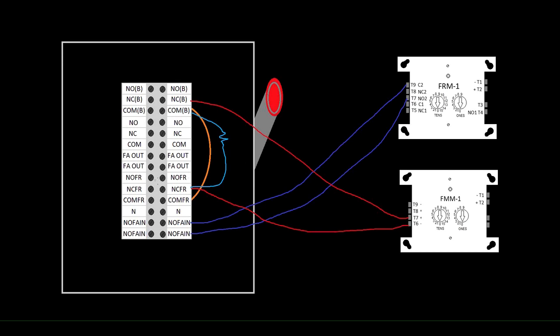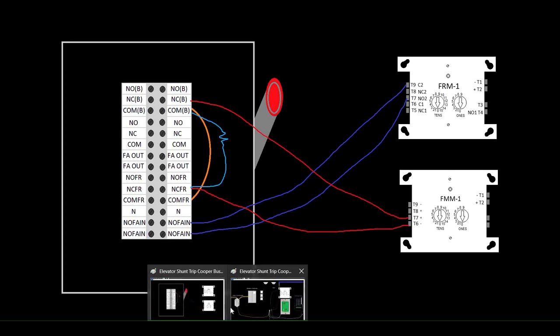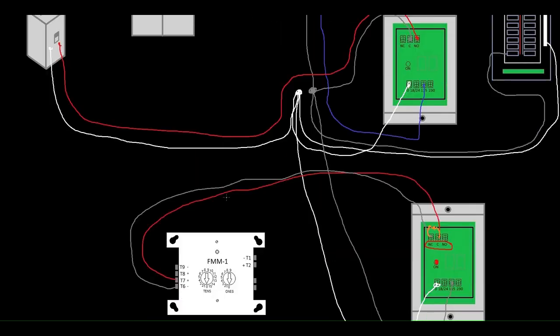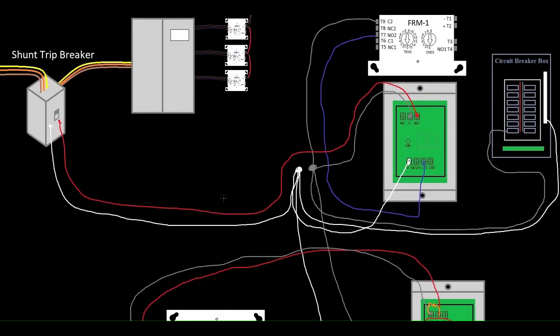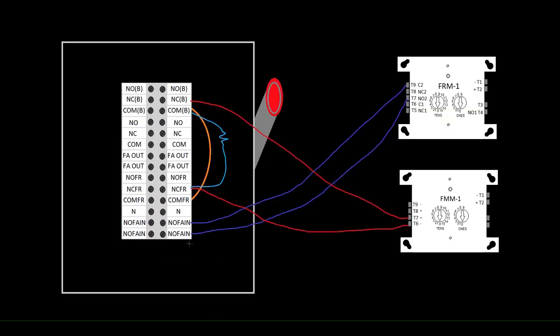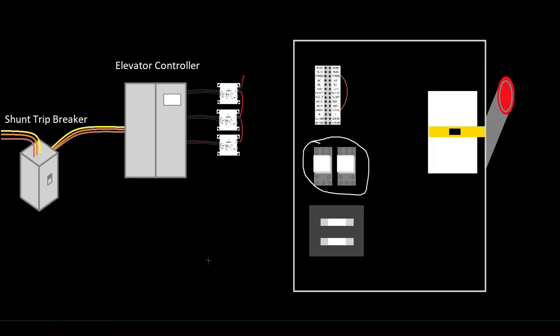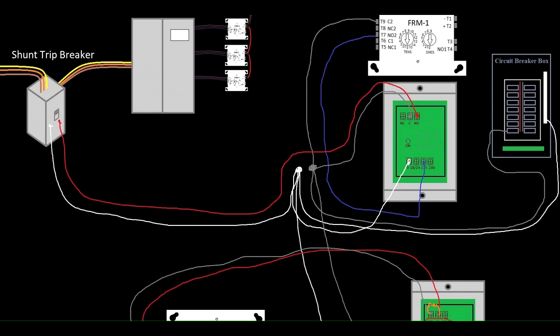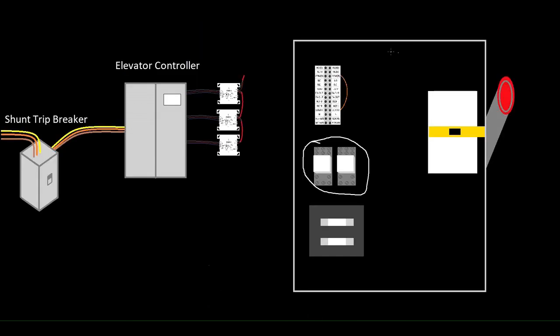And it really is just as simple. This is all there would be to shunt if you bought the right piece of equipment. So if you look at all the wiring stuff that went into the other method of doing it, I really do think that this newer way is a better bet. And maybe this is more common in other parts of the country or other parts of the world, but from where I'm working I think I've seen this a handful of times at most. In most cases you're probably not going to know when you're bidding a job or ordering equipment for the job if this is a type of breaker that they have installed. So I would recommend erring on the side of caution. You need the same number of addressable relays and monitor modules, you know, just one of each for shunt trip. I would come prepared with those MR-101s or 201s. I personally carry those on my truck just for situations like this. But I would prepare for the worst, which would be the other situation, and then hopefully this is the equipment that gets ordered and then you don't need the two MR-101s.